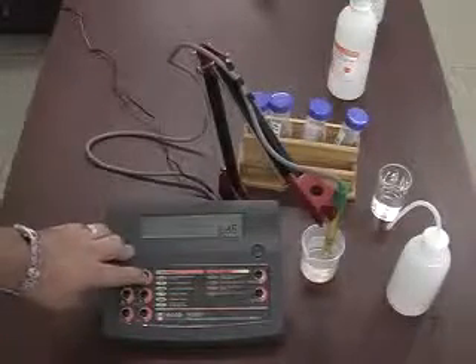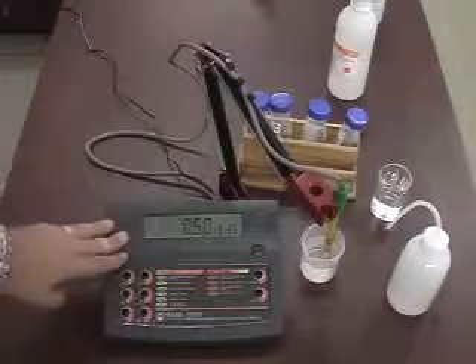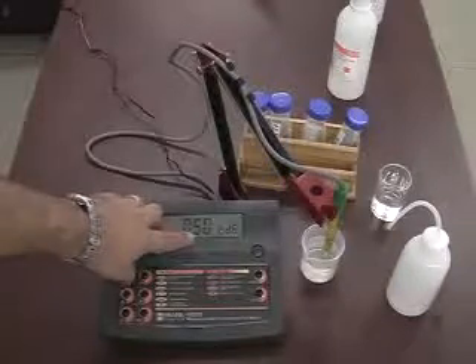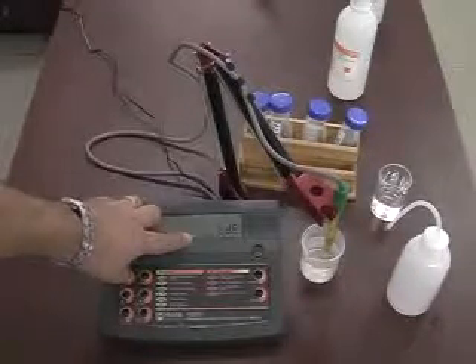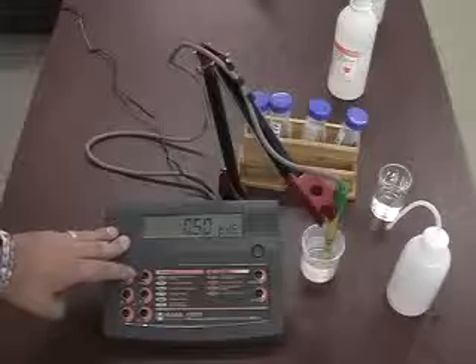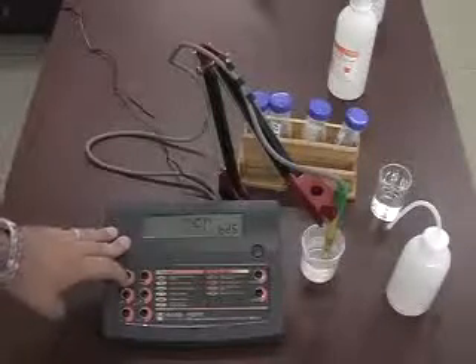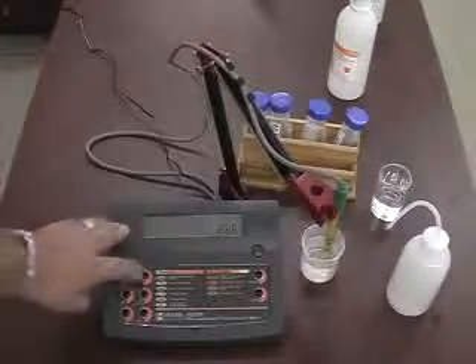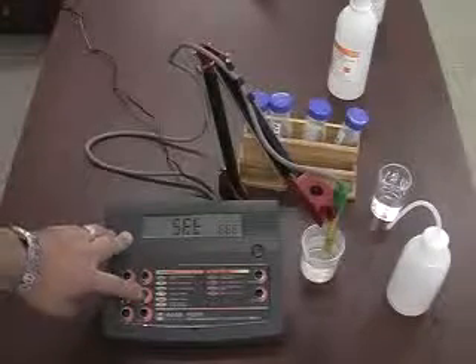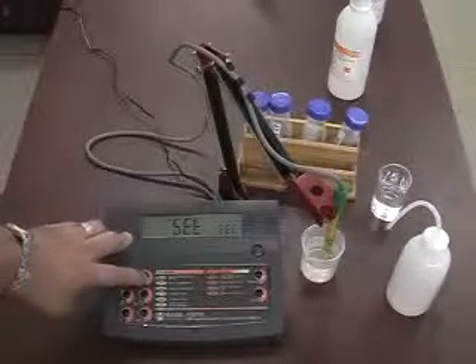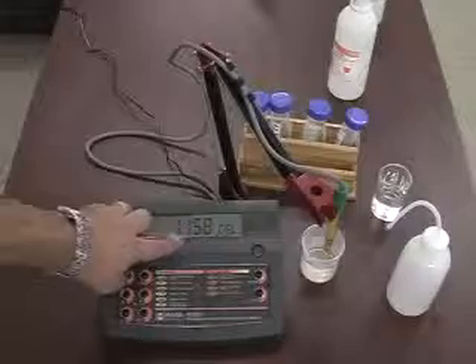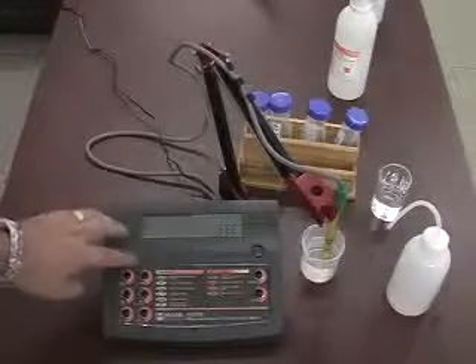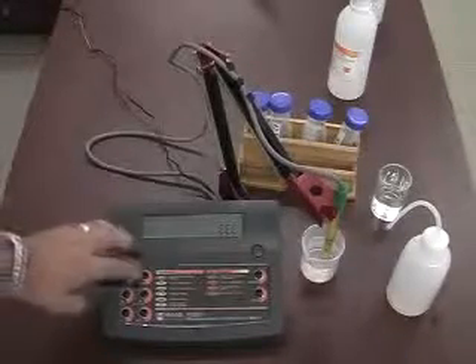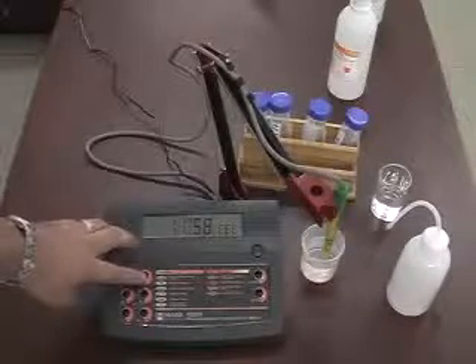TDS conversion factor, which, again, normally for all conductivity measurements, we take the measurement, multiply it by 0.5, and we convert to TDS. Some applications require 0.65 or 0.68. The meter gives you the option to make those adjustments. The cell constant, the default value is 1.0. After calibration, you will get an adjustment with that based on the standardization of the electrode.